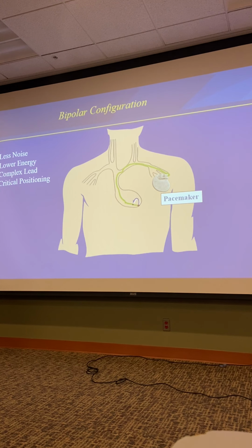The other option is bipolar pacing. There are two electrical connectors very close to the tip of the lead, and the electrical circuit is just going from one to the other. The amount of energy that's needed is very small, and there's a significantly reduced likelihood of any noise coming from the muscles of the chest wall or elsewhere, interfering with the ability of the pacemaker to see the electrical activity of the heart. So there's less energy needed from the battery, less noise can be picked up from the chest wall, but it's a more complex lead.